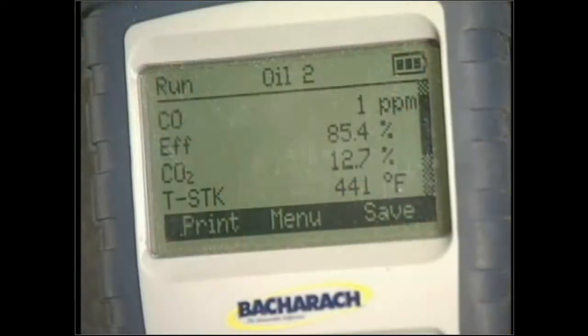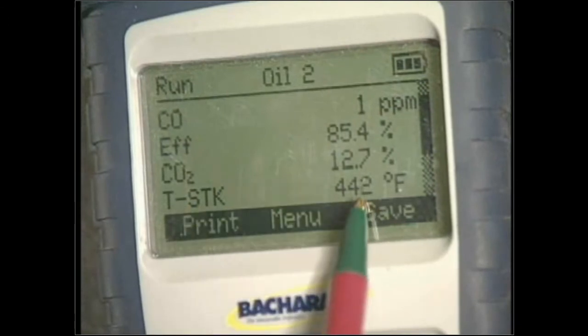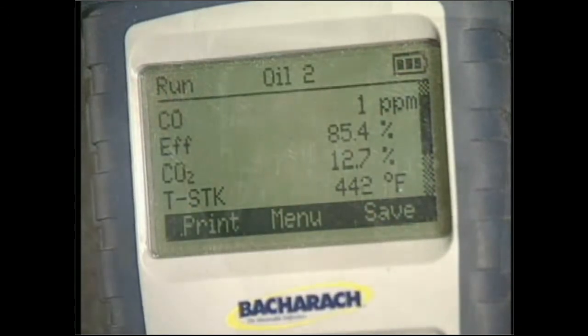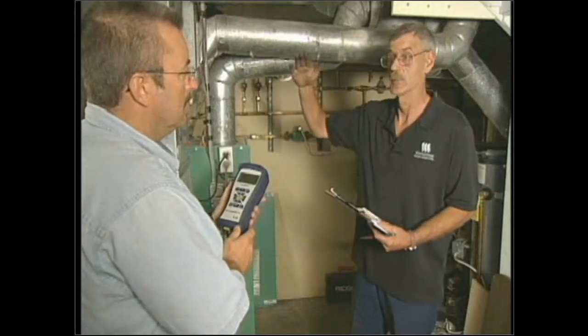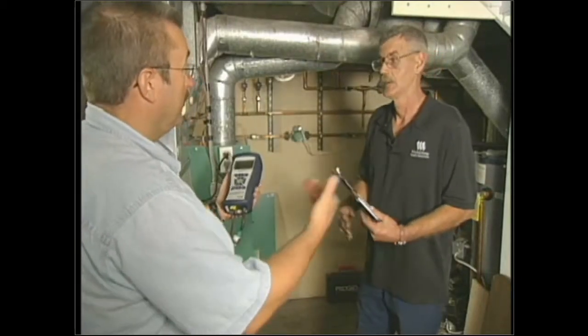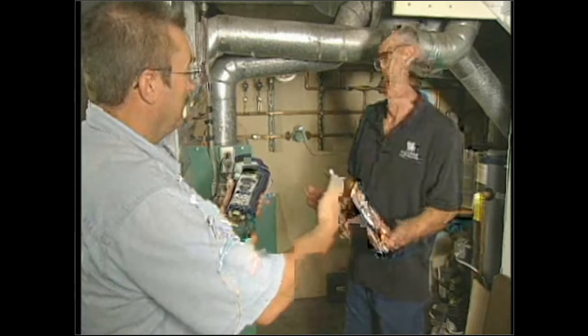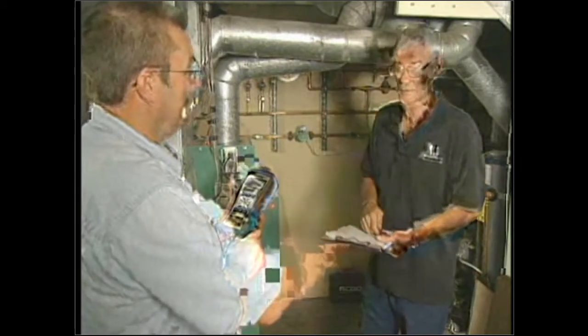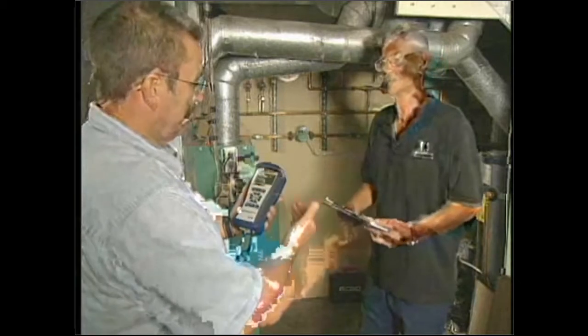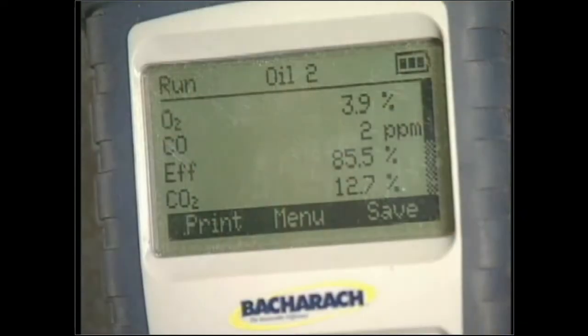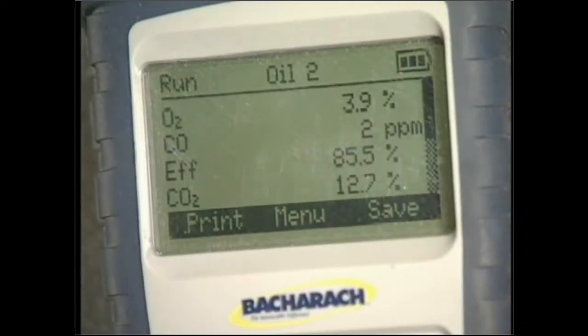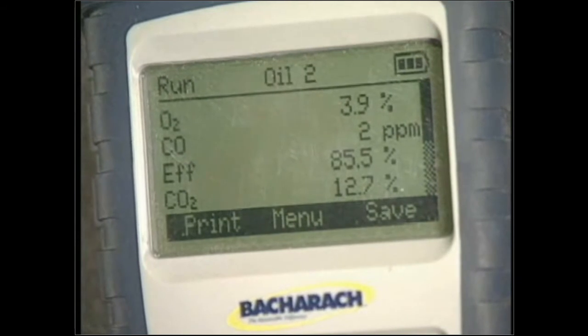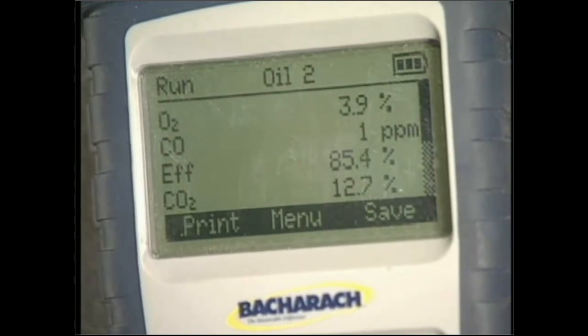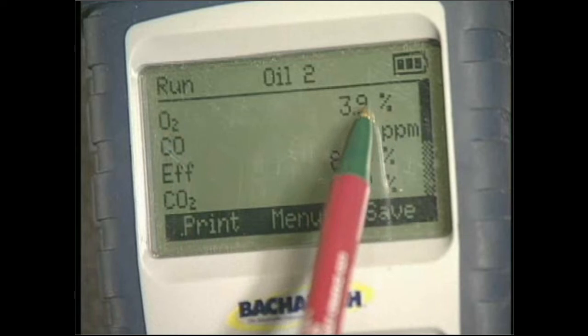Okay. So then we wait till the steady state. Steady state is when the stack temperature stops climbing and stays stable at one point. Sometimes it takes several minutes to get there, especially on an oil unit, because the metal's heavier and the flues are bigger. In this case, the stack temperature leveled out in the mid-400s. Then we took the oxygen reading and documented that. We documented the CO, which is about 1 to 3 parts per million. Then we measured the efficiency, which was 85.1 or 85.2, bounced a little bit.